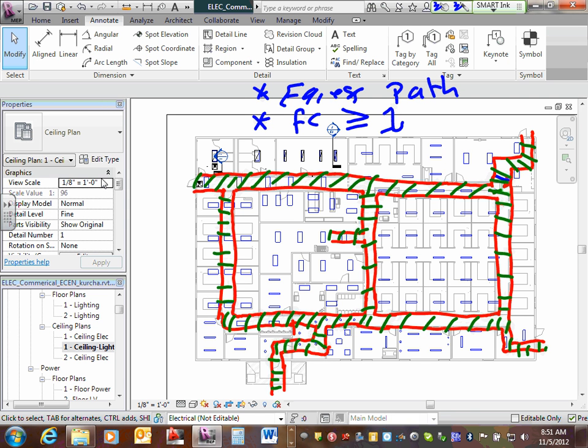Now the smart people, guys, get the exit and the egress in one combo. Okay, so let me tell you where. So here's my placement. What I'm going to be using, guys, is a fixture that looks like this. Exit with a light here, light 1, light 2. You guys are familiar with bug eyes? They're called bug eyes. This is the best one that you can use, right? Because it gives you both exit and egress. Can I have thumbs up, Chad? Exit and egress, no problem. Okay, get your exit and egress at the same time.